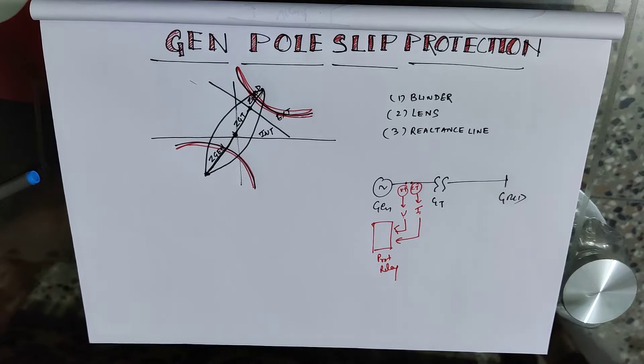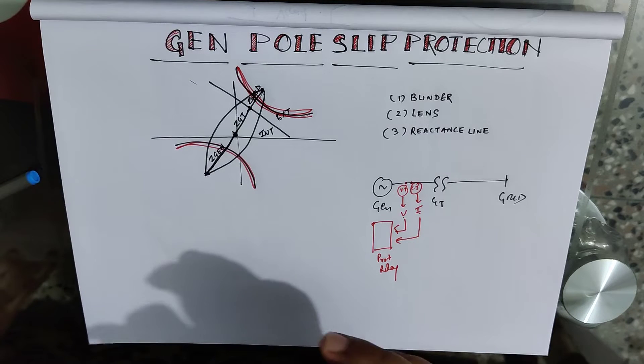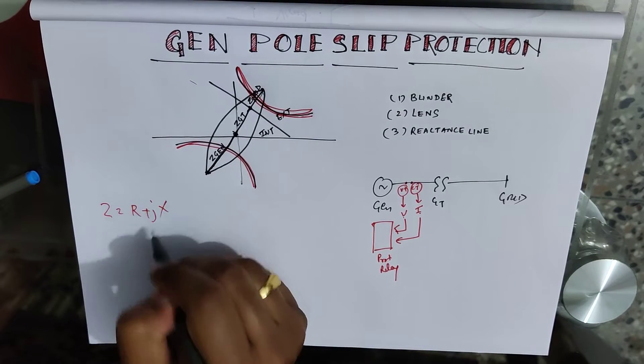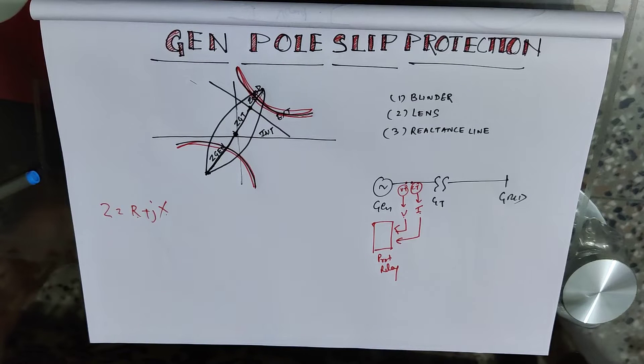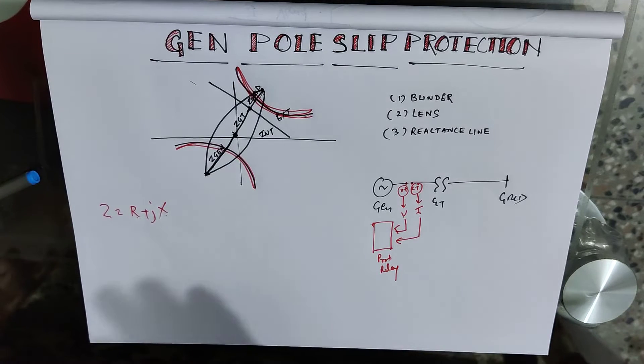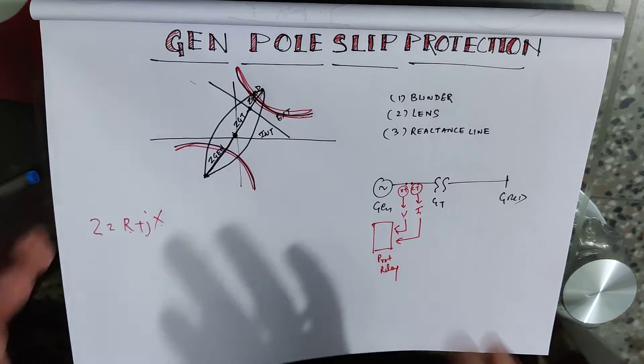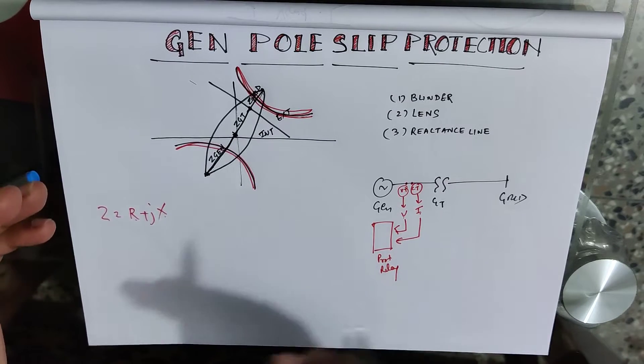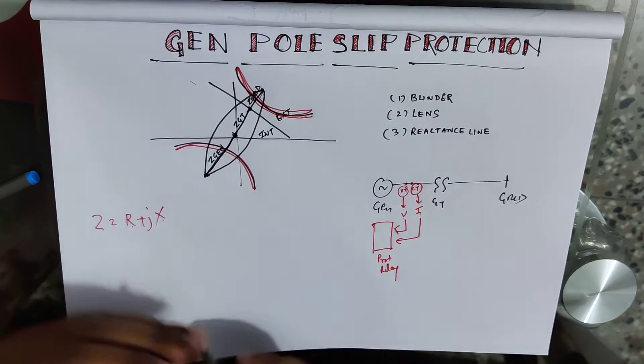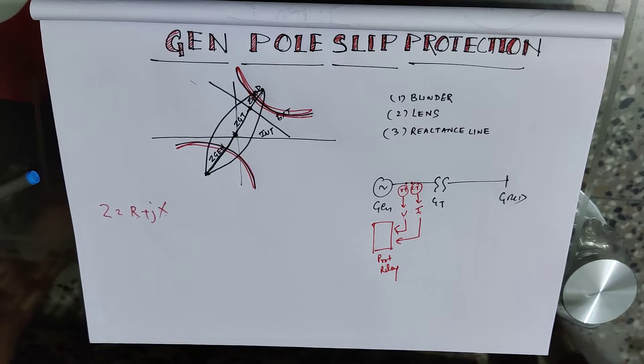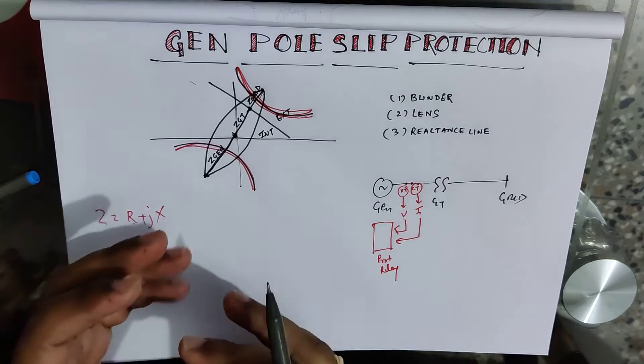The relay is present in the generator relay panel. From this voltage and current, the generator relay will calculate the impedance — impedance is nothing but the summation of resistance and reactance. If that impedance enters the locus of pole slip protection, stays in the locus for a particular period of time, and then comes out, the relay will count it as a slip. If the number of slips experienced by the relay is more than the setting, then the relay will issue a trip command. This is how pole slip protection operates.